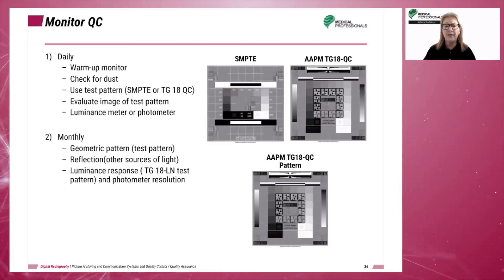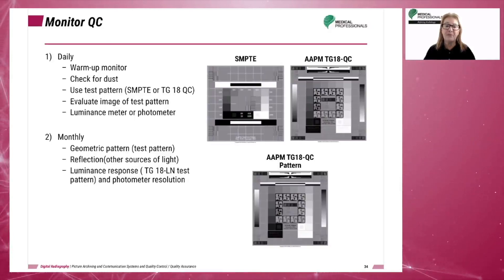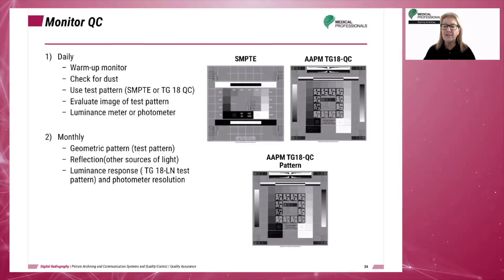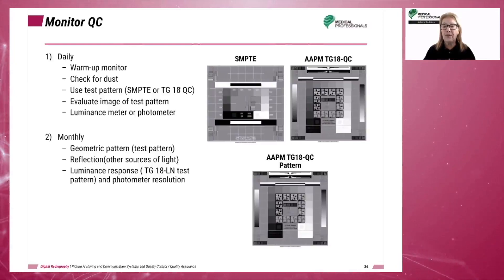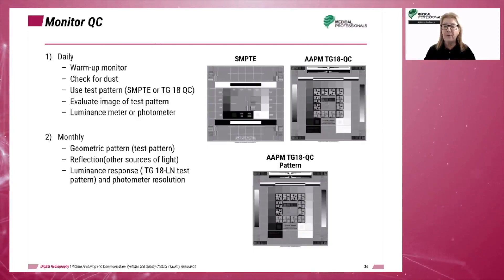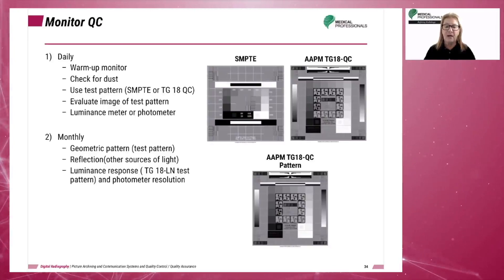To evaluate geometric distortion, look for variations in the shape of the displayed image; the borders and lines of the test pattern should be straight. Luminance, reflection, noise, and glare can be evaluated with a luminance meter or with a photometer and the test pattern. There are a number of AAPM-TG18 test patterns available for testing other imaging modalities and additional aspects of the PACS.